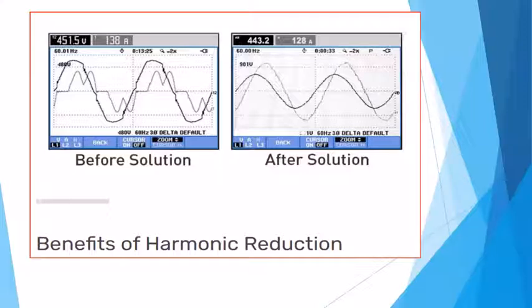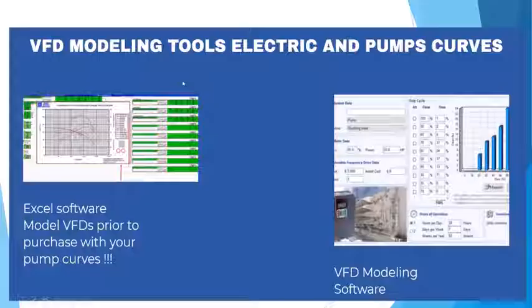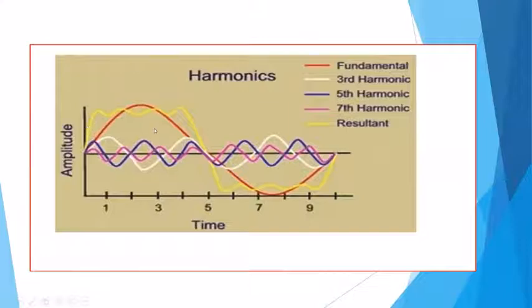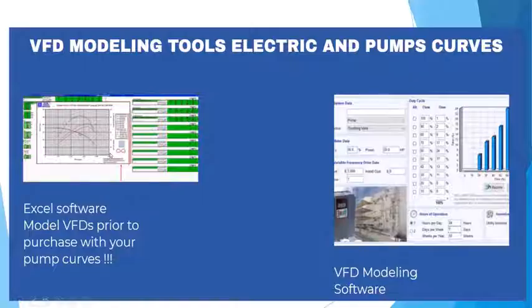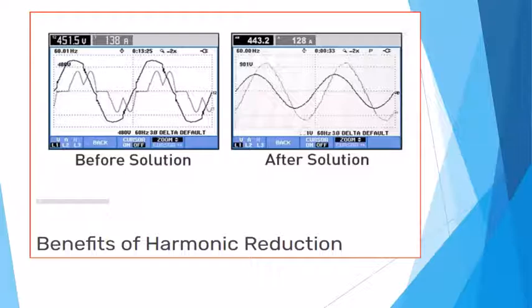So that's why sometimes your power meter doesn't always match up with what you're getting billed for, because the power company gets those resultant values in their power line where they're reading the meter, and you're not getting it there. So it's important that we keep that power clean coming in, both the current and the voltage. Here's the voltage, here's the current, and you can see before, it had all these blips and information, but the resultant amount of power was up in here. So that's why the power company sees this times this, the resultant, and that's where your power readings can be quite different from what you're actually getting billed for.